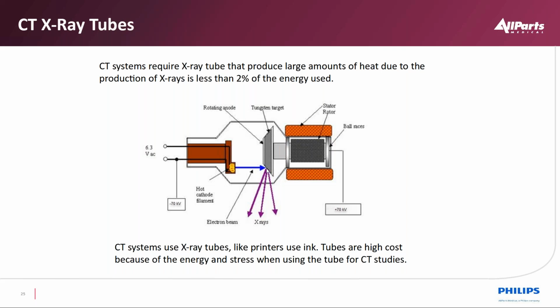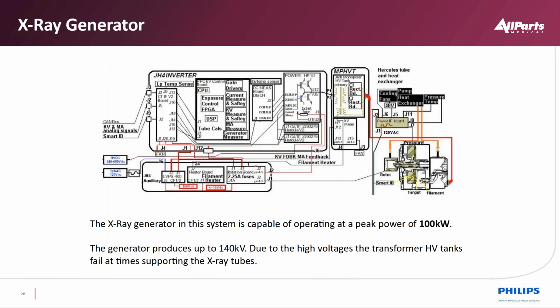Resolution-wise, a smaller filament is the advantage, but it would burn our target. So at some point in time when we're doing larger body studies, our resolution is not as important as getting the whole body in, so they'll leverage the large filament for those types of studies. But we're dealing with voltages of 140,000 volts potential here on this setup right here. So if you think about it, in CT, we're dealing with computers with a memory voltage of 1.5 volts, and we're going all the way up to potentially 150,000 for testing, but we typically max at 140.